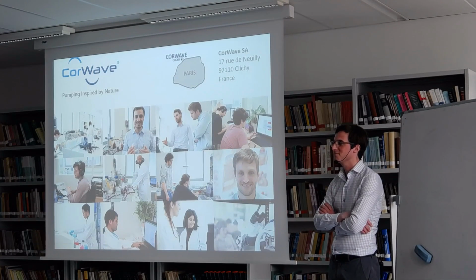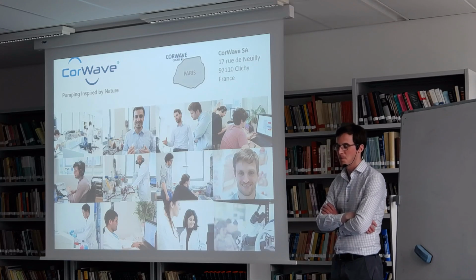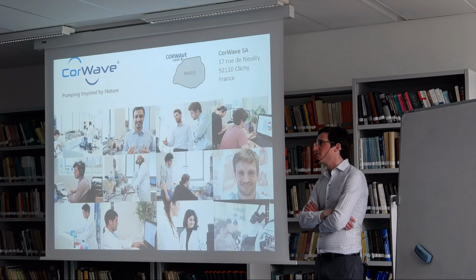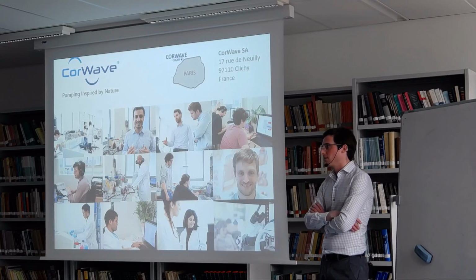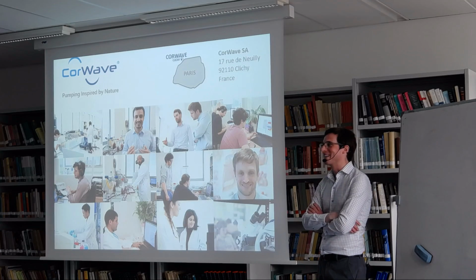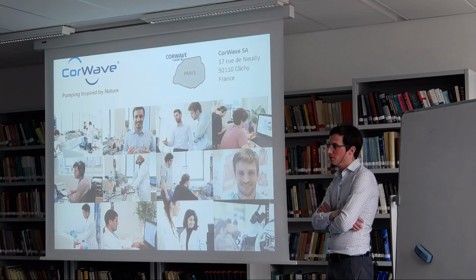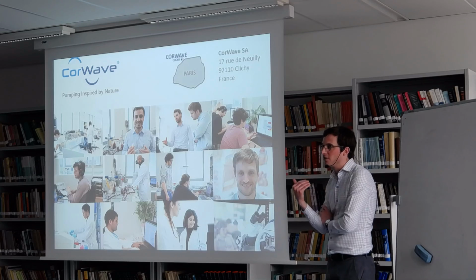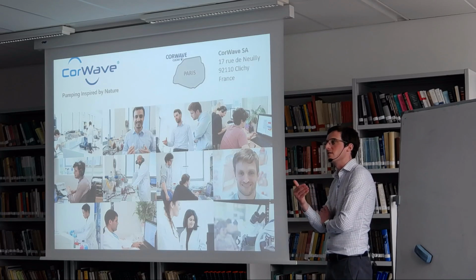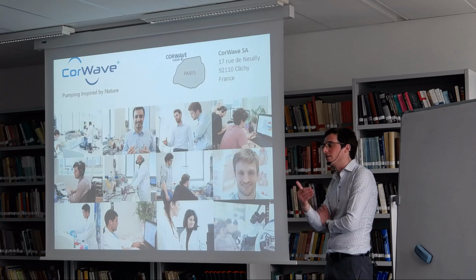Thank you for the presentation. How do you keep your device in synchronization with the blood flow or the heart pumping? There are several ways to do it. I would say the most straightforward way is that there are, to a certain extent, integrated sensors in the pump already, meaning the electrical signal. By measuring the electrical signal, one can measure if there's a flow acceleration or deceleration through the pump, because it influences the load on the pump, and you have a signal on your electrical signal when the heart is pulsating.